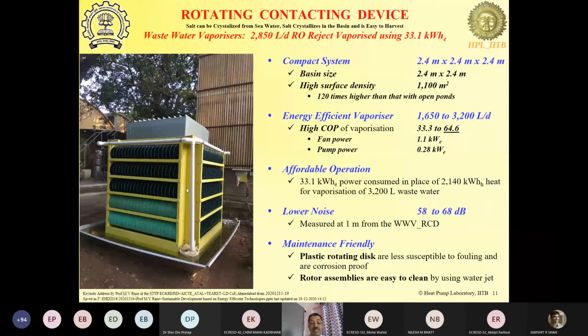It has been already licensed as a wastewater vaporizer for industrial effluent treatment. And the beauty of this is we have handled very high TDS, right up to 2,70,000 TDS in industrial situations, and yet there is no scaling up of the disk, and there are no issues regarding corrosion and other things. And we have deployed these systems as evaporative condensers, as salt pan evaporation enhancers, and so on and so forth. And for this energy efficient vaporizer of wastewater, our COP in a humid place like Mumbai was around 33. This was the photograph while it was being tested just outside our lab. And in the plant in Barmer in Rajasthan, we had got COPs as high as 64.4.